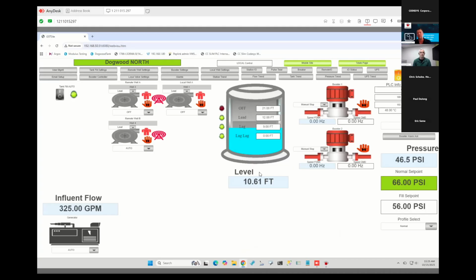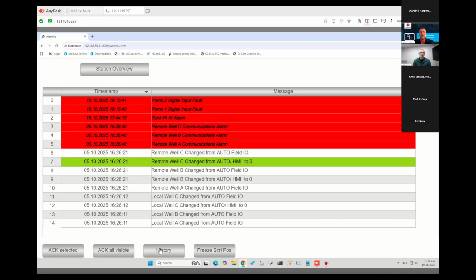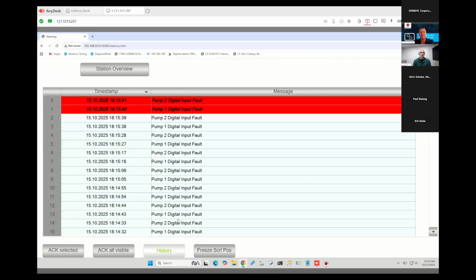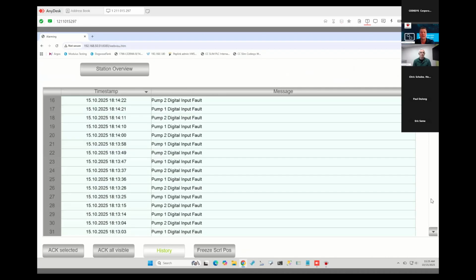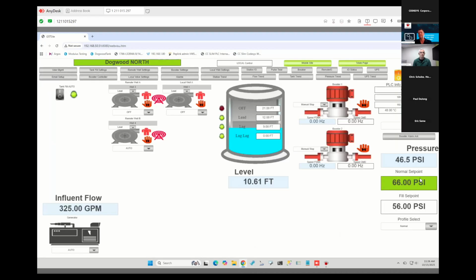So that's the configurable side of it. The other part is really, how do you monitor, how do you support this? So through the same thing, we've got alarming. So the alarms are built in, and we're also using the alarming for operator monitoring. So what that means is if I come in here and I change my pressure set point here on the screen or over SCADA, this also is a Modbus remote. So from Modbus TCP, I can do all of this through a SCADA system. We've got it all mapped.